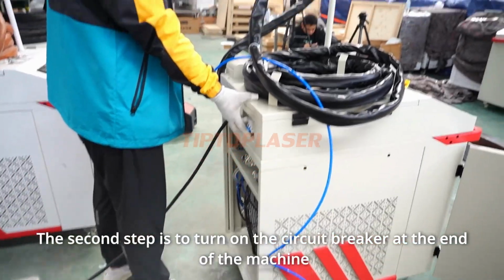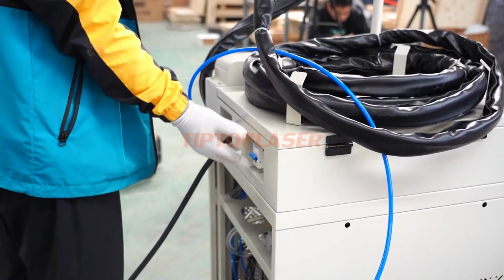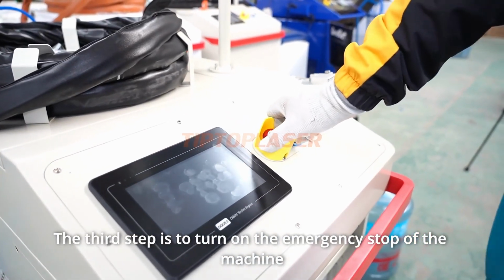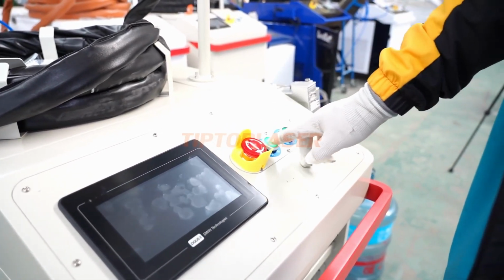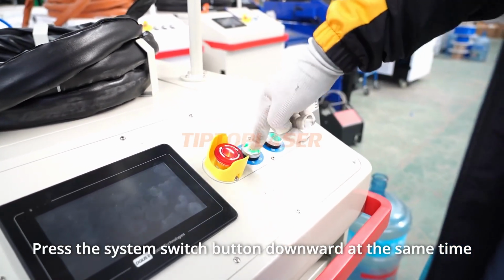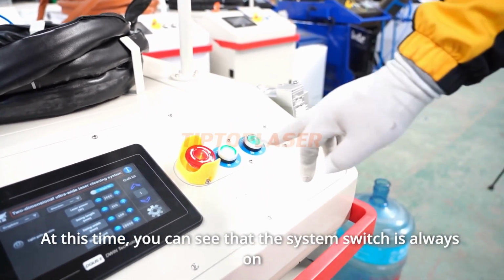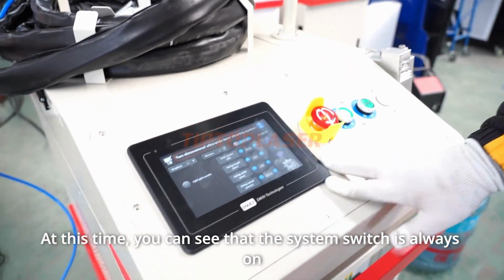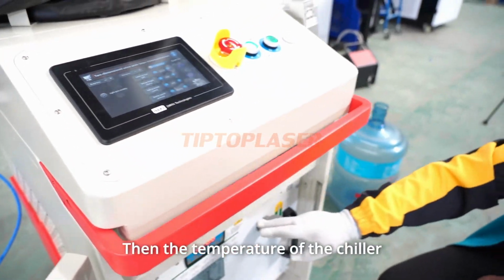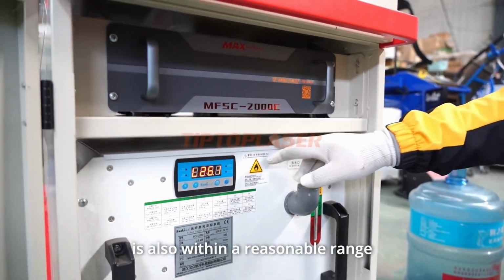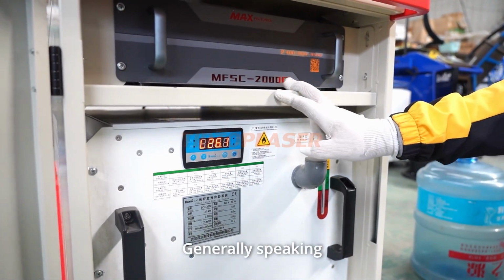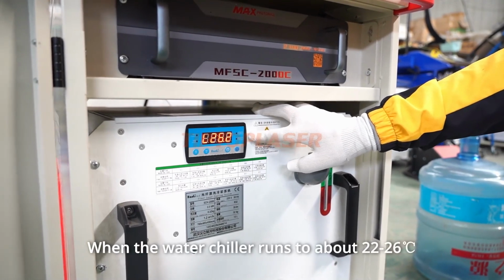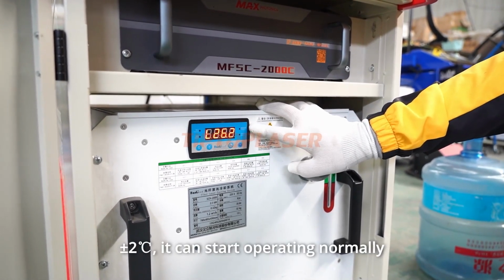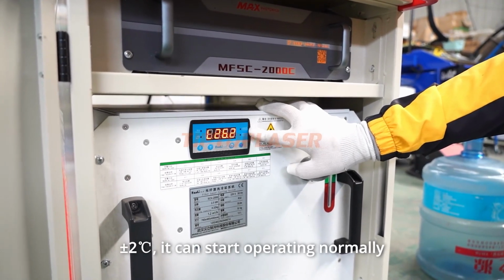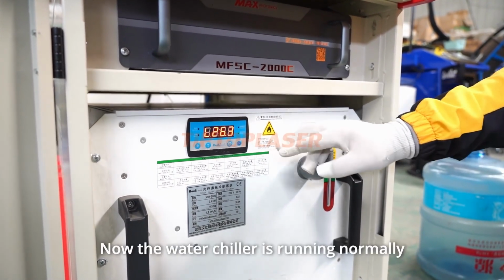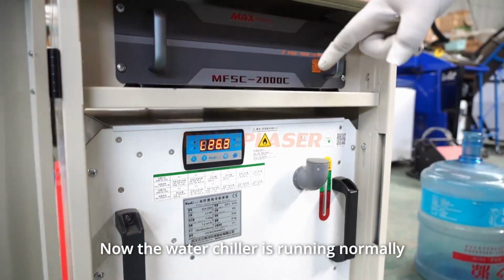Put it back. The second step is to turn on the circuit breaker at the end of the machine. Open it upwards. The third step is to turn on the emergency stop of the machine. Press the system switch button downward at the same time. At this time, you can see that the system switch is always on. Then the temperature of the chiller is also within a reasonable range. Generally speaking, when the water chiller runs to about 22 to 26 degrees plus or minus 2 degrees centigrade, it can start operating normally. Now the water chiller is running normally.